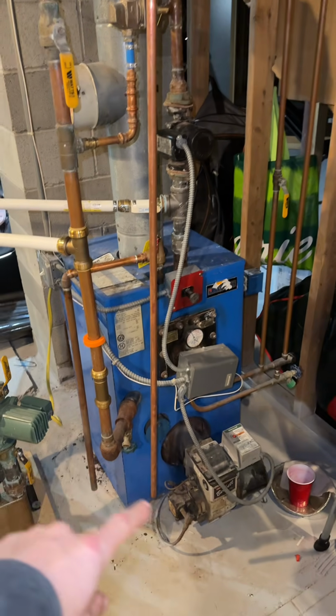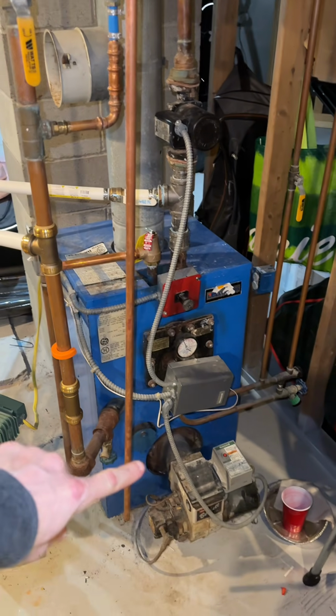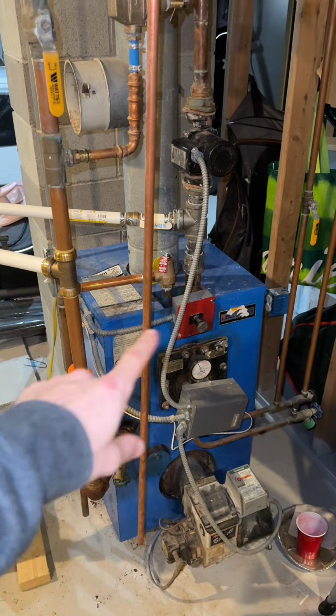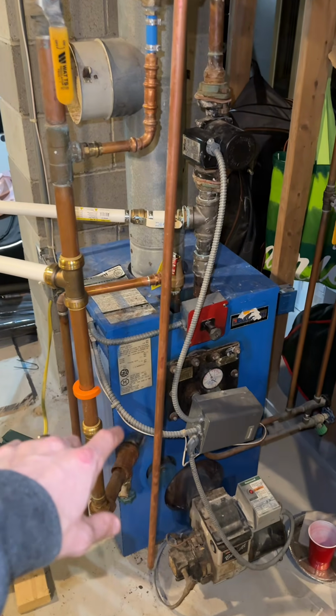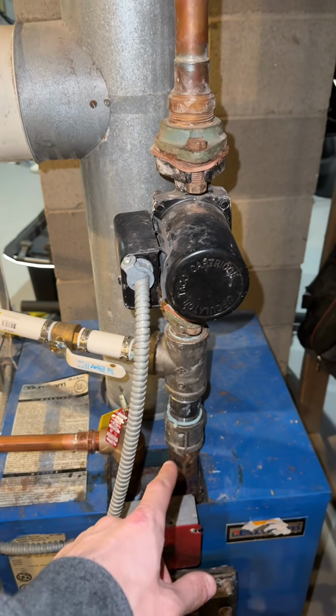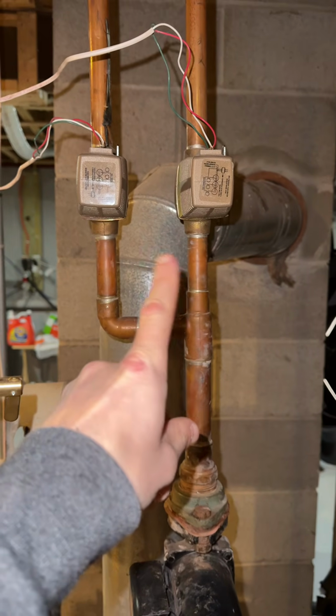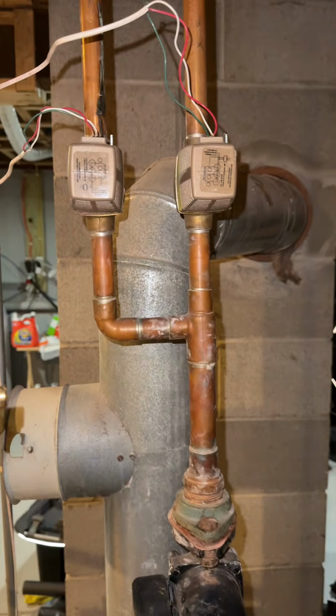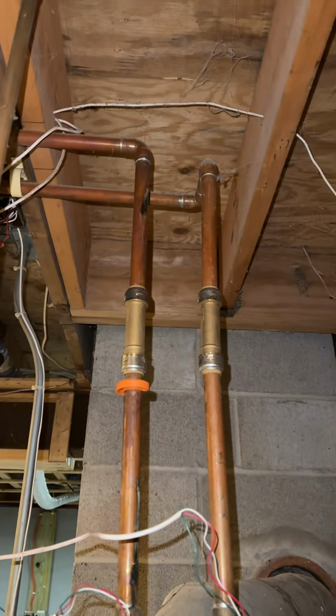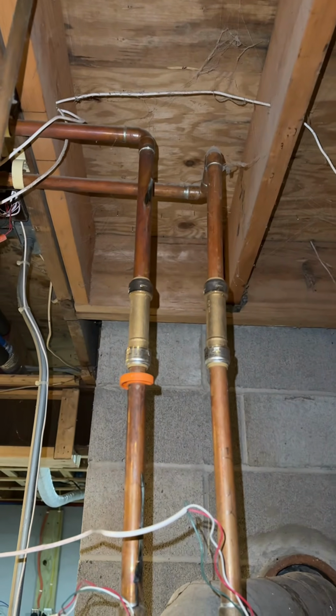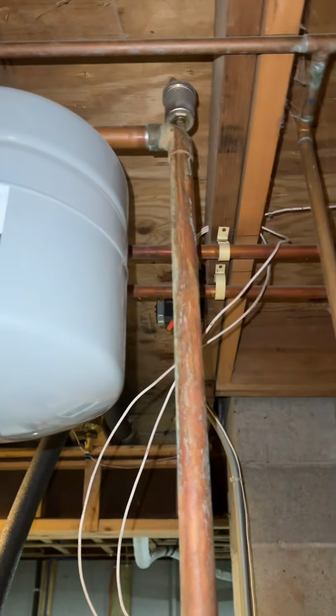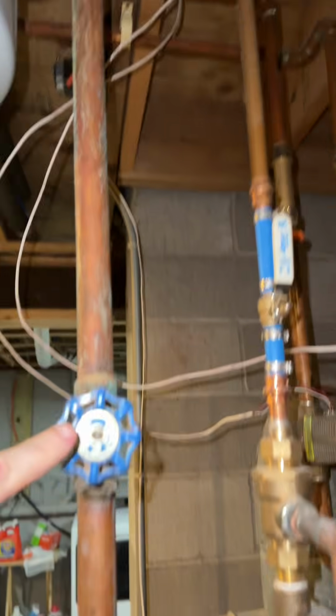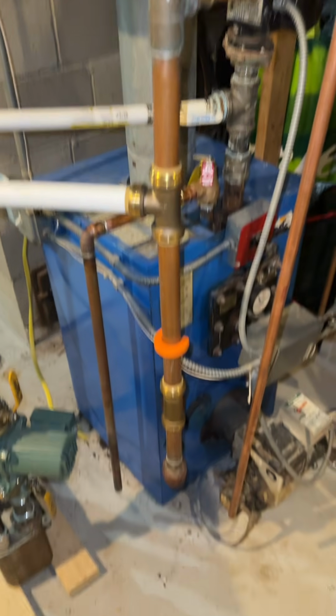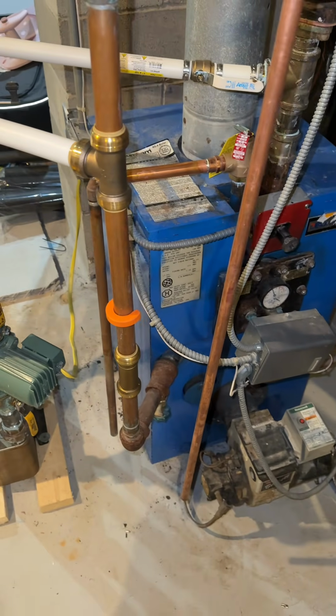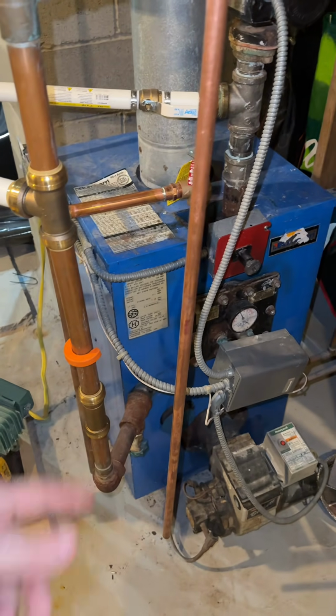This is an oil boiler. You got the oil burner here, firebox, and then there's a water jacket. That water jacket is then heated, and water comes up here through this pump, through these two valves, whenever my thermostats are calling for heat. So that goes up and goes to the baseboard radiant heat. It then comes back on this line and goes back into the boiler to get reheated and cycled again.